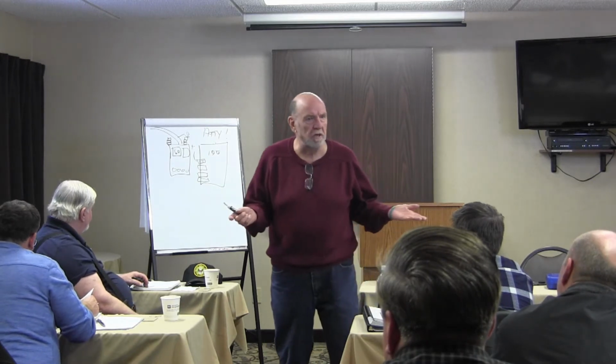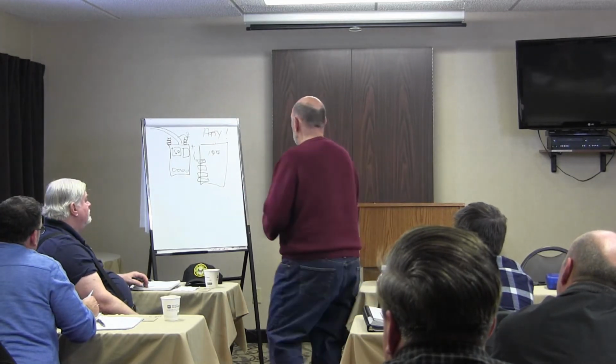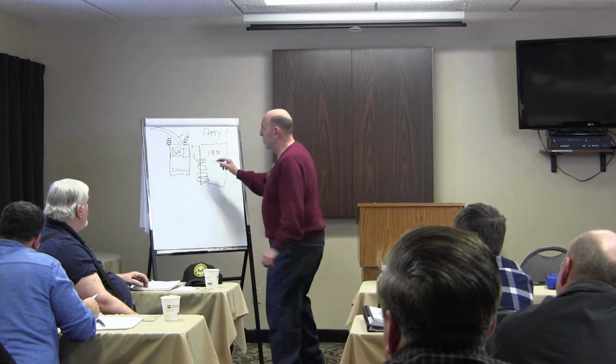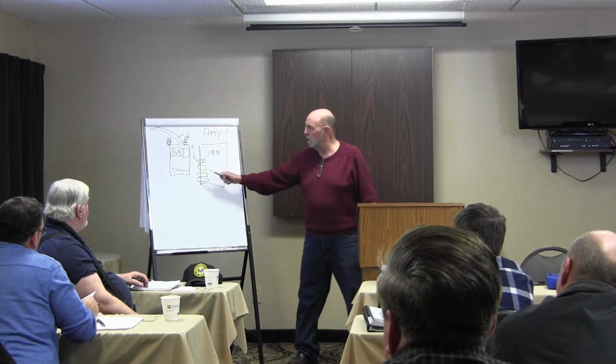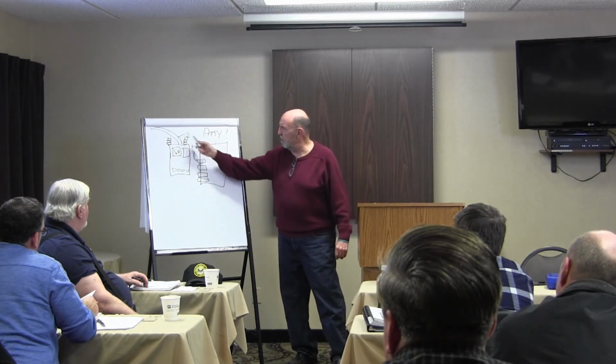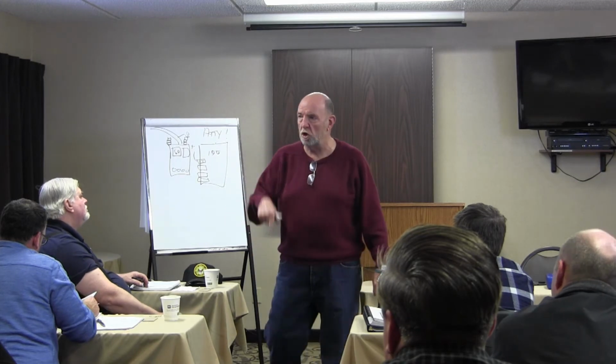The realtor looks at me, but it's only $800. And it is. It's only about $800 to do a simple 100 amp panel, and to replace that, just run the circuits over here, bang, it's $800. Why, Dan, are you calling it a major? It's because I want to make sure the insurance company, and everybody knows, I said this is an issue, because when they go to get this house insured, it's not going to get insured. It's going to cause problems down the road. So let's address it now.